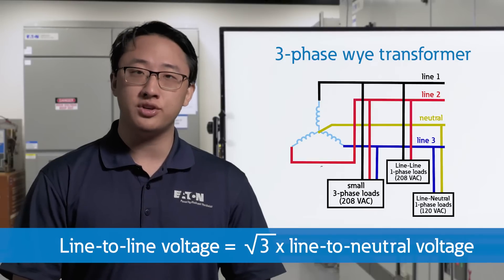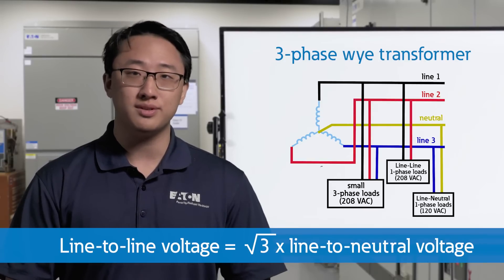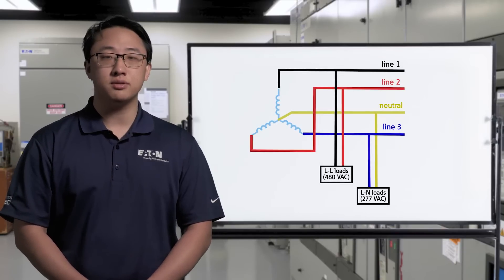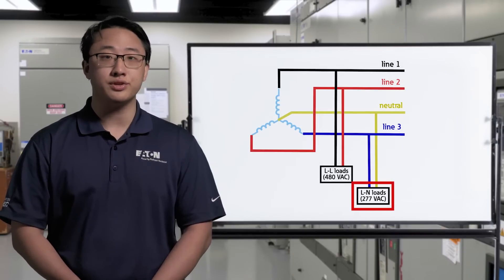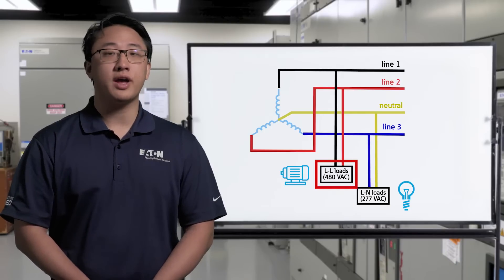The 208 comes from the transformer relation line-to-line voltage equals square root of three times line-to-neutral voltage. A common higher power version of the same Y configuration is available with 277 line-to-neutral voltage, most often for lighting, and 480 line-to-line voltage, usually for heavy motor loads.